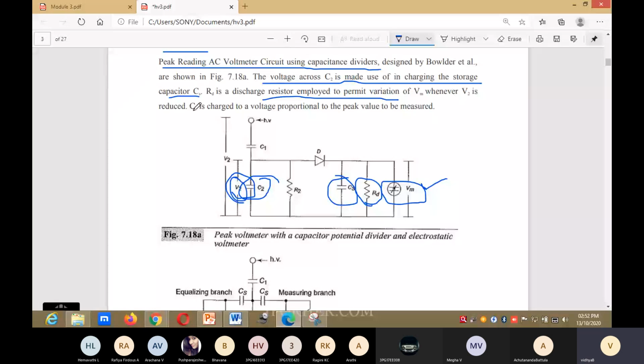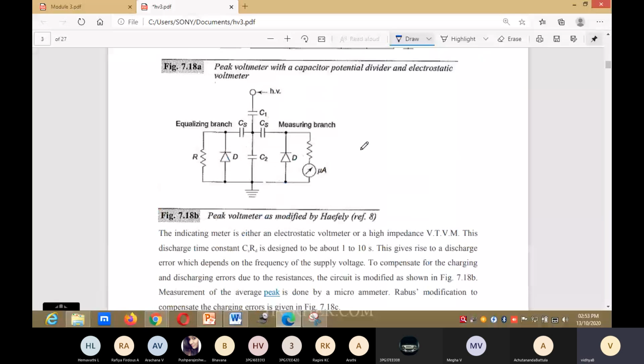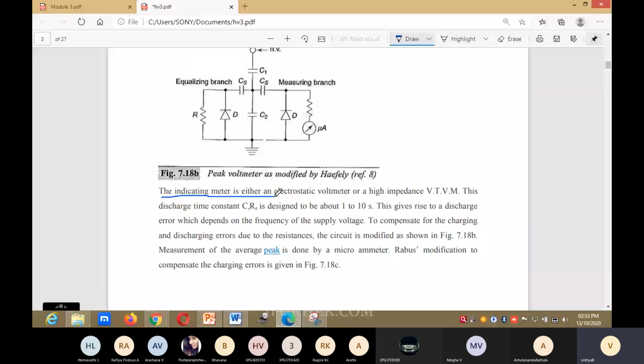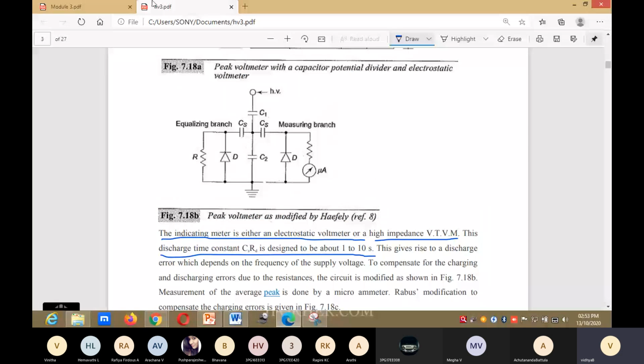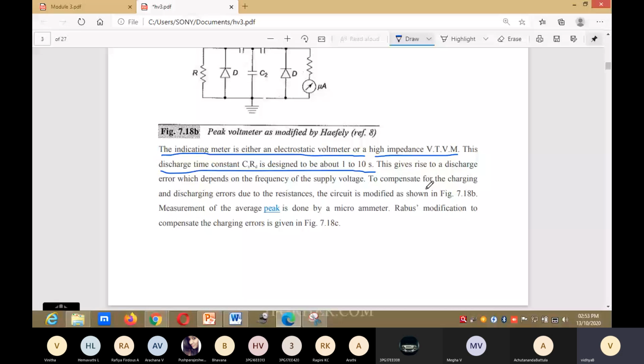CS is charged to a voltage proportional to the peak value to be measured. The indicating meter is either an electrostatic voltmeter or a high impedance VTVM. The discharge time constant CS RD is designed to be about 1 to 10 seconds, and this gives rise to a discharge error, which depends on the frequency of the supply voltage.